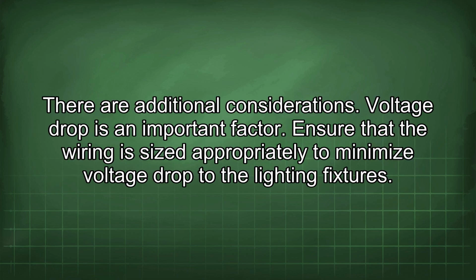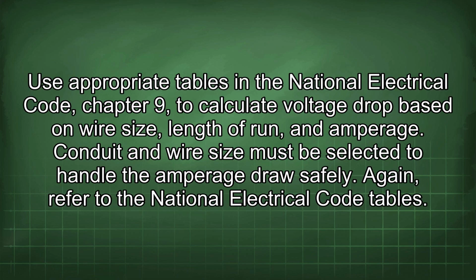There are additional considerations. Voltage drop is an important factor. Ensure that the wiring is sized appropriately to minimize voltage drop to the lighting fixtures. Use appropriate tables in the National Electrical Code, Chapter 9, to calculate voltage drop based on wire size, length of run, and amperage. Conduit and wire size must be selected to handle the amperage draw safely. Again, refer to the National Electrical Code tables.